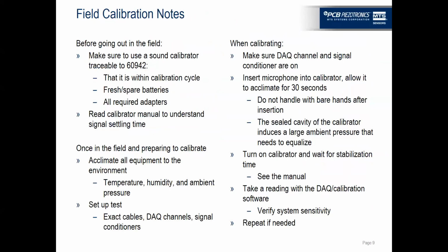Once you are in the field and preparing to do the calibration, make sure that all of the equipment that you have is acclimated to your environment. Microphones are very sensitive to temperature, humidity, and ambient pressure change. All three of these factors will have a determination of what the sensitivity of the microphone is. Also your calibrator, make sure it's at the same temperature, humidity, and ambient pressure, because if you take a microphone that's at one temperature and a calibrator that's at a different temperature and put them together, you're going to have some weird results because the calibrator will be trying to make the microphone its temperature and vice versa.